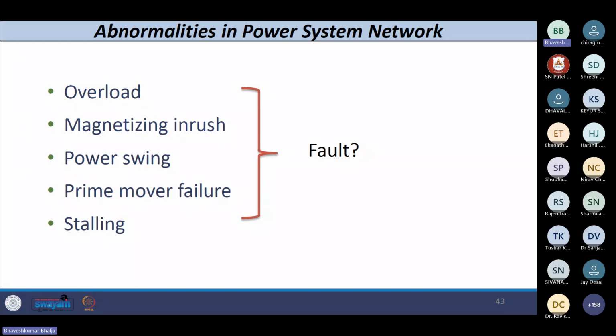When you energize the transformer, let's say a power transformer, 400 kV to 20 kV, then usually we energize the transformer during an unloaded situation. That means no load is connected. So the secondary side load is not there, or if it is there, it is lightly loaded. And then on the primary side, we are going to energize the transformer.